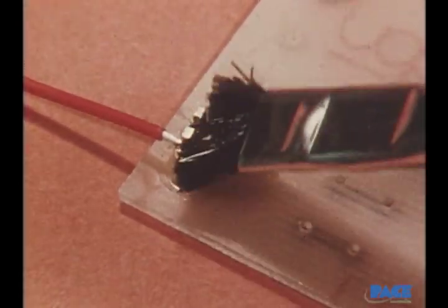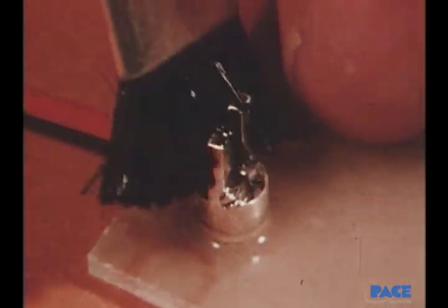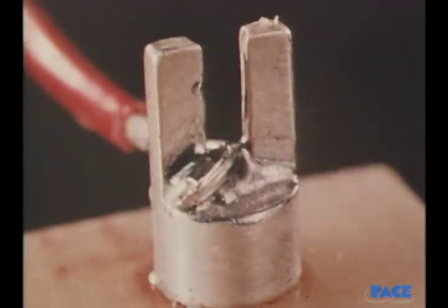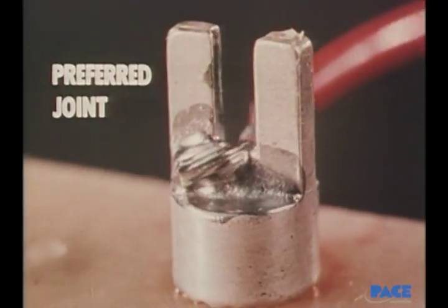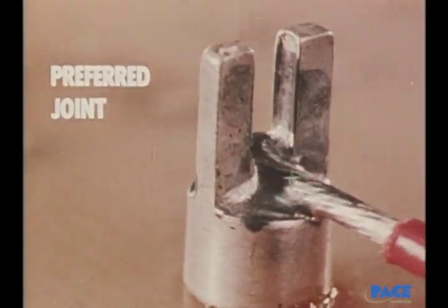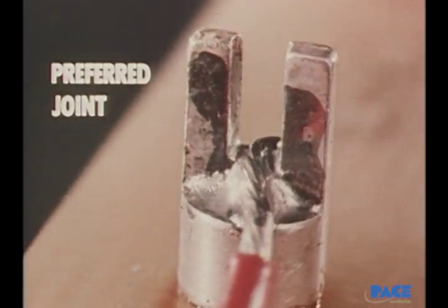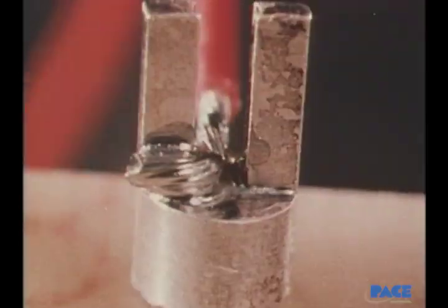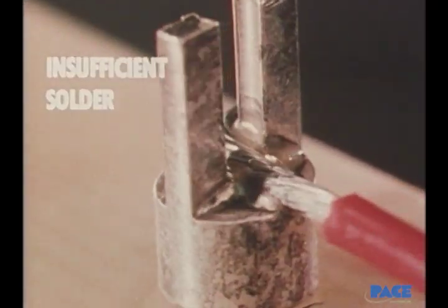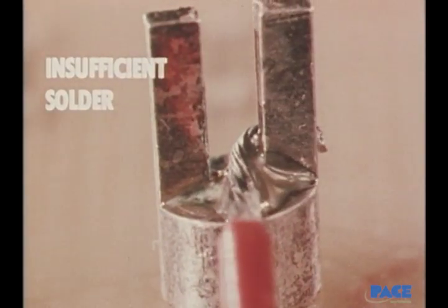The joint is then cleaned. These are the three surfaces that should be in contact with the wire when it's properly wrapped around the terminal. The joint is clean, smooth, and bright with an undisturbed surface and a concave fillet exists between conductor and terminal. For comparison, here is a joint that is unacceptable because it has insufficient solder and the end of the lead extends beyond the diameter of the terminal.